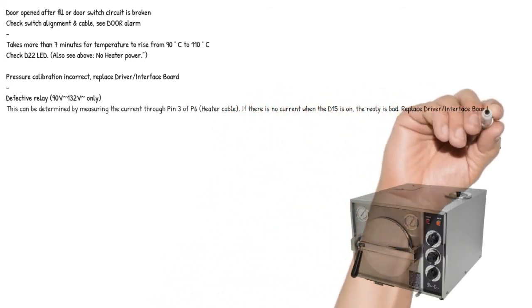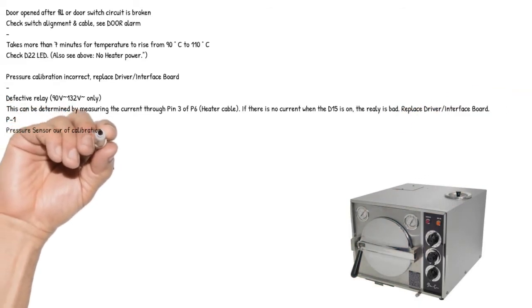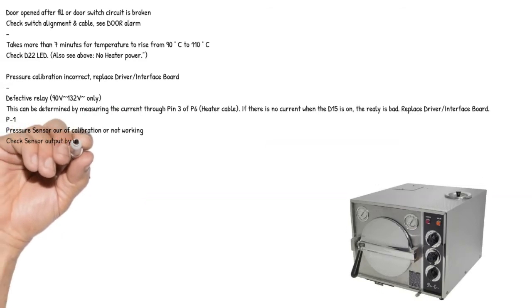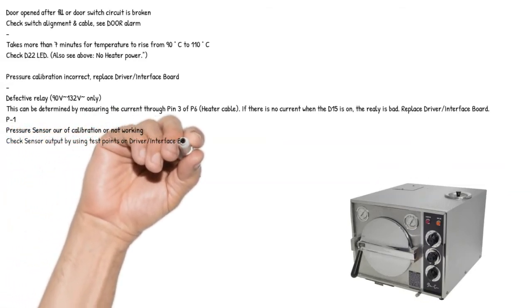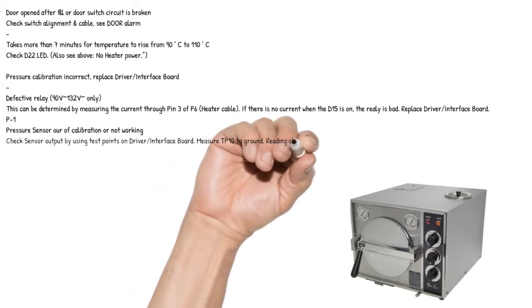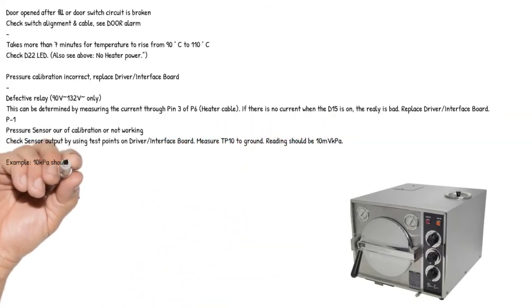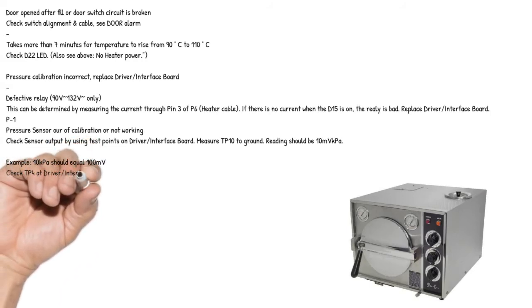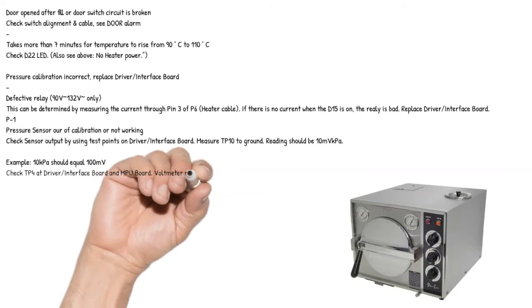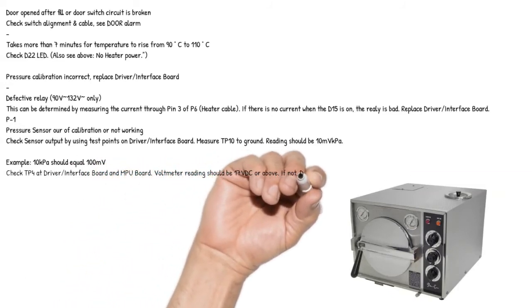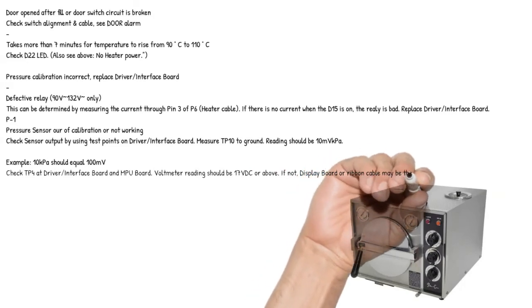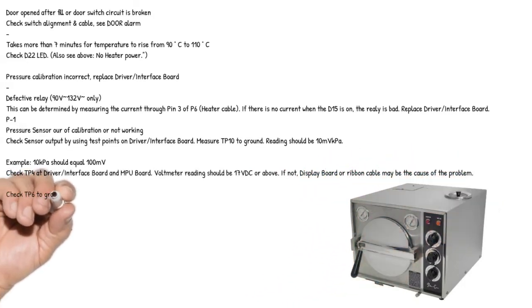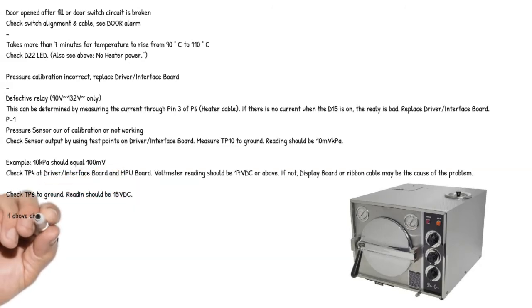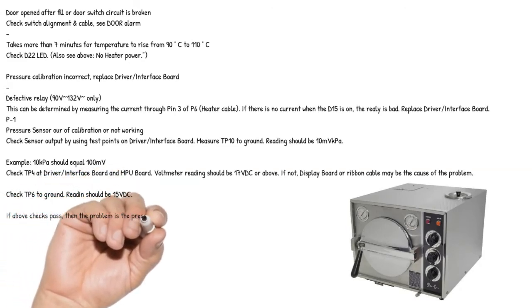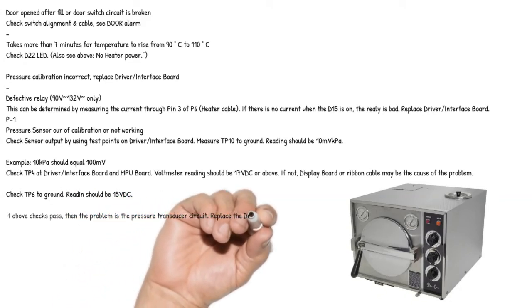Replace driver/interface board. P1. Pressure sensor out of calibration or not working. Check sensor output by using test points on driver/interface board. Measure TP10 to ground. Reading should be 10 mV/kPa. Example, 10 kilopascals should equal 100 millivolts. Check TP4 at driver/interface board and MPU board. Voltmeter reading should be 17 VDC or above. If not, display board or ribbon cable may be the cause of the problem. Check TP6 to ground. Reading should be 15 VDC. If above checks pass, then the problem is the pressure transducer circuit. Replace the driver/interface board.